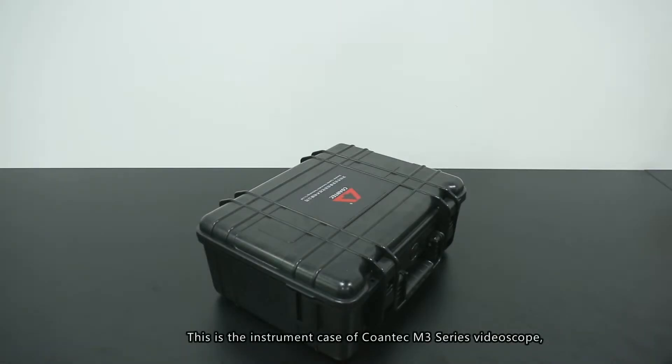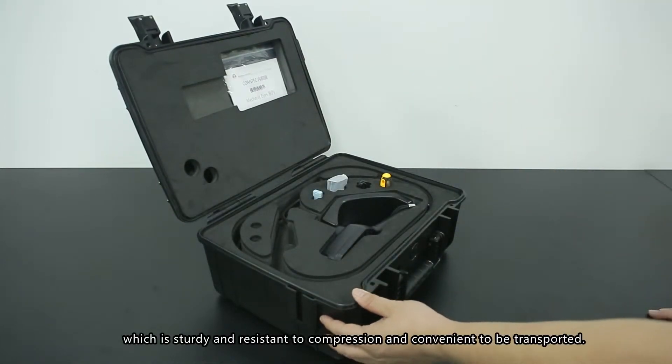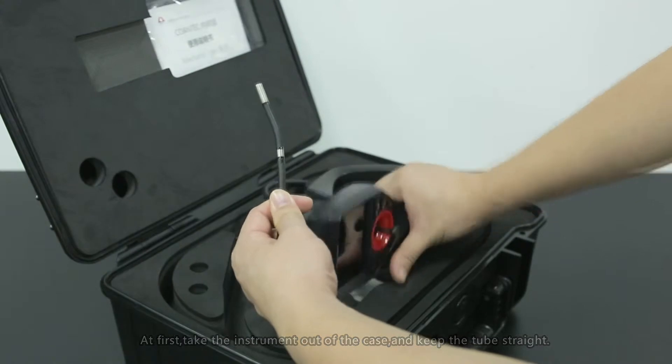Now let me show you how to operate this video scope. This is the instrument case of the Coantec M3 Series Videoscope, which is sturdy, resistant to compression, and convenient for transport. First, take the instrument out of the case and keep the tube straight.